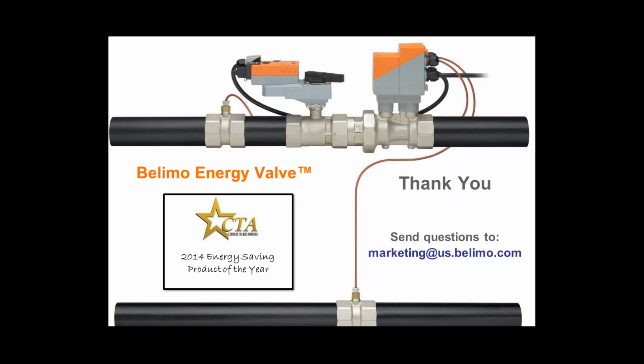But if you don't have control of your coils, what will likely happen is that some of them will be starved, because you're going to provide overall less flow. The building is demanding this high flow because we're having inefficient heat transfer in certain spaces. Those places will still demand high flow, and if your overall head to the building is reduced, then we have the potential to starve far out.